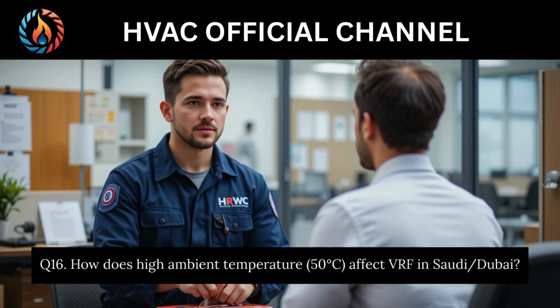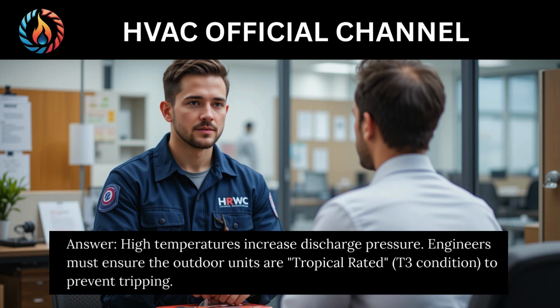Q16. How does high ambient temperature, 50 degrees Celsius, affect VRF in Saudi and Dubai? High temperatures increase discharge pressure. Engineers must ensure the outdoor units are tropical rated, T3 condition, to prevent tripping.